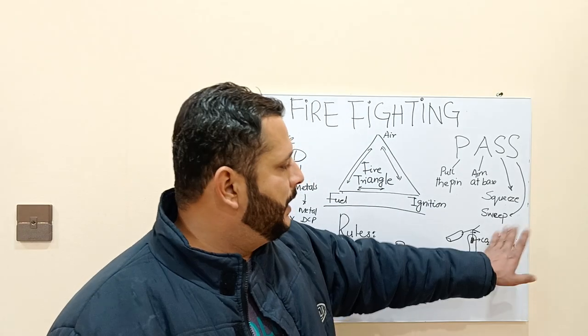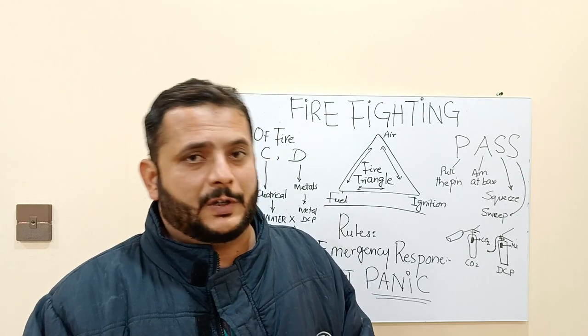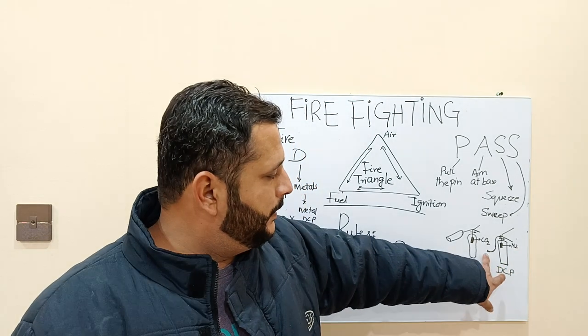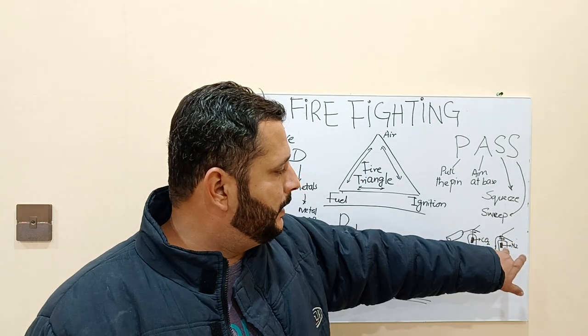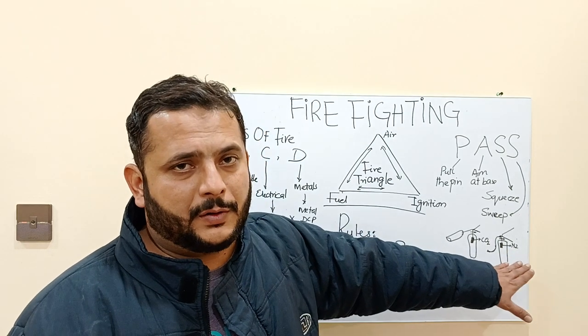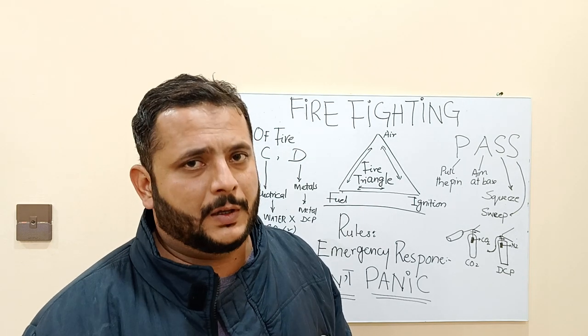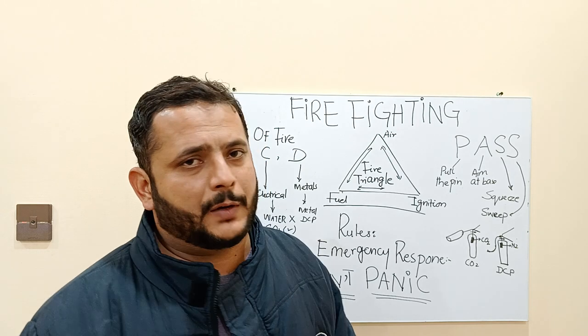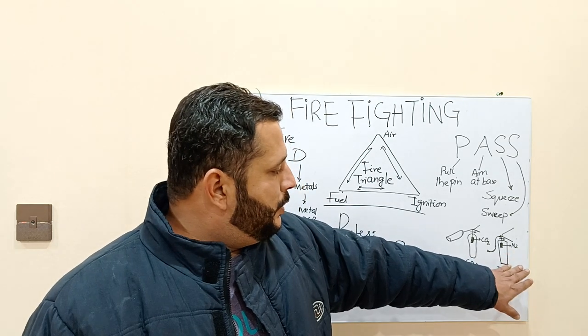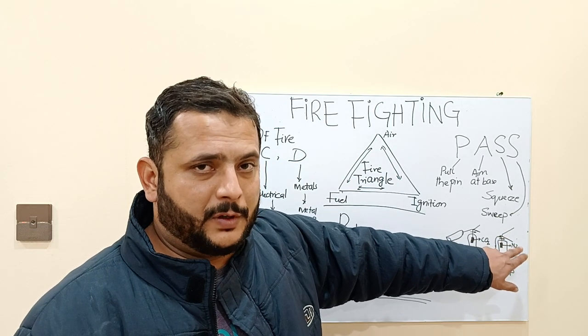There are visual evidences from which you can identify which type is DCP and which is CO2. For the dry chemical powder extinguisher, it has a hose, trigger, pin, and a nitrogen gas cartridge inside the shell, and it is filled with powder. There are different sizes of DCP fire extinguishers — 3 kg, 6 kg, 8 kg, 10 kg, and so on. Some come with a trolley, with large sizes of 30 kg or 50 kg.